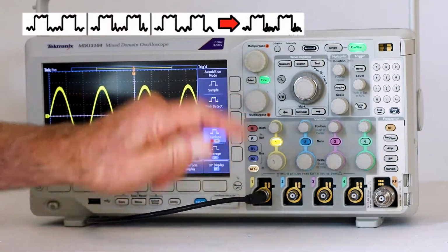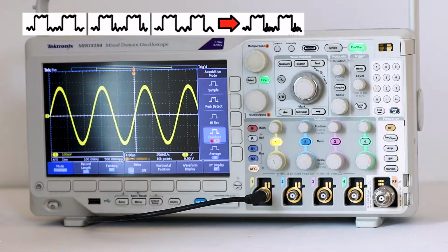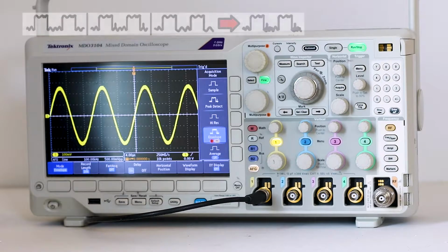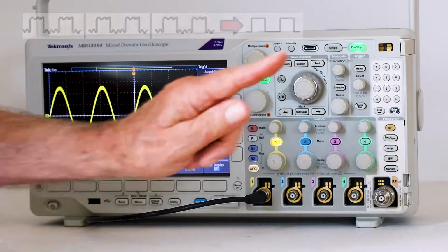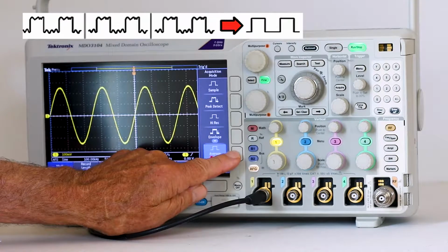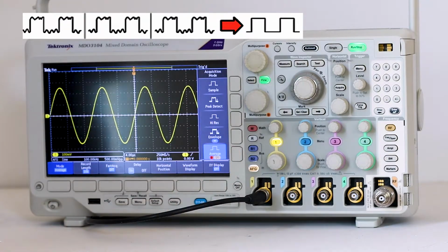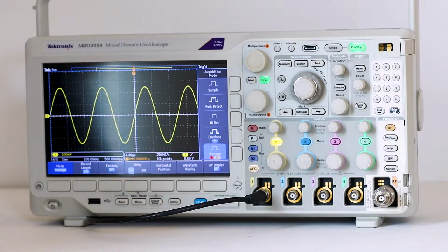Envelope mode finds the highest and lowest record points over all acquisitions. Envelope uses Peak Detect for each individual acquisition. Average mode calculates the average value for each record point over a user-specified number of acquisitions. Average uses sample mode for each individual acquisition. Use average mode to reduce random noise.